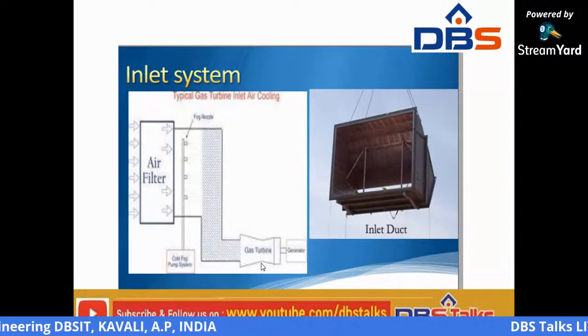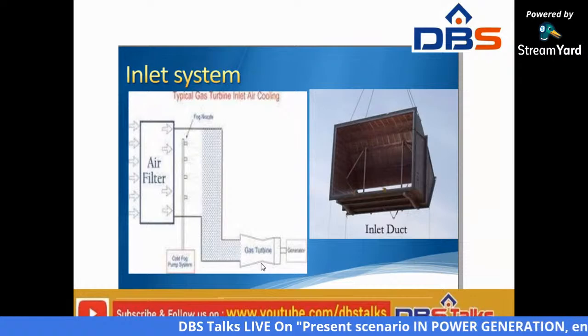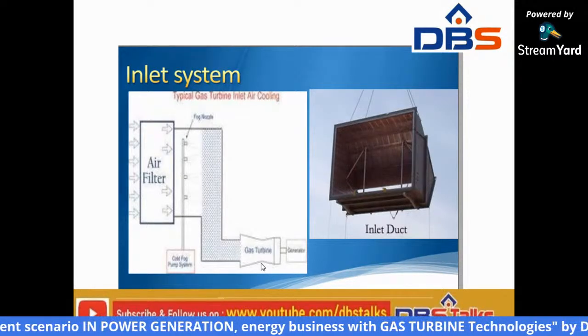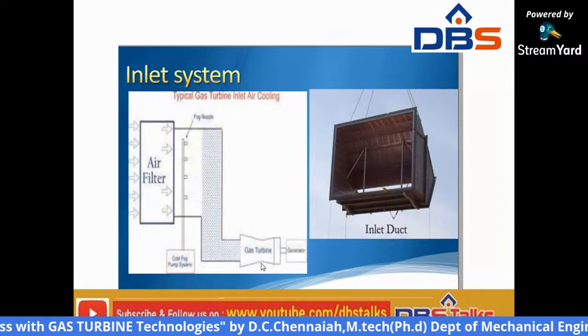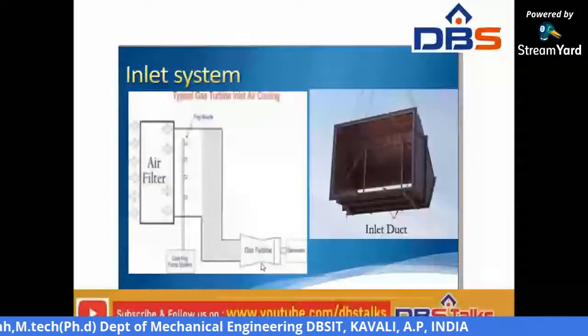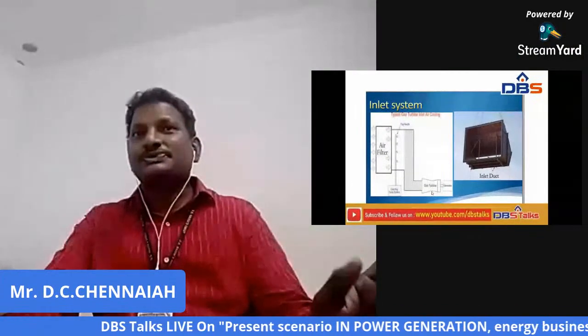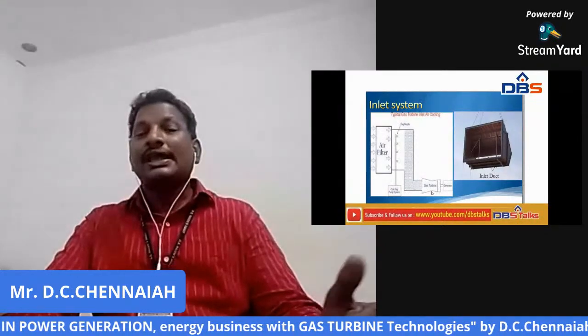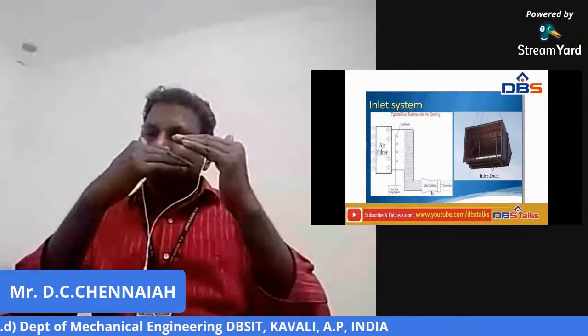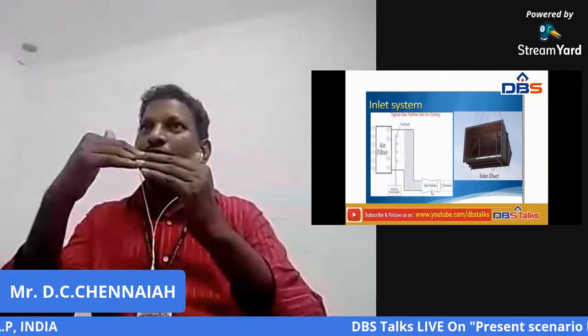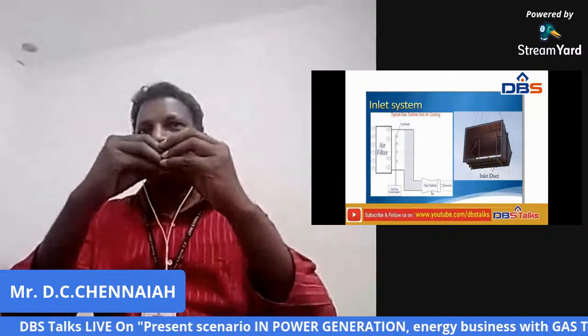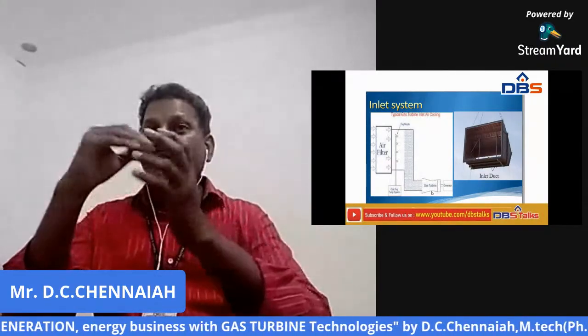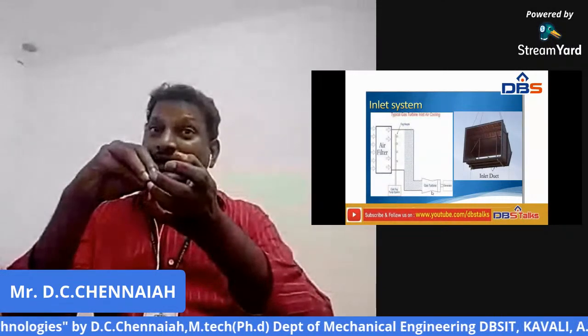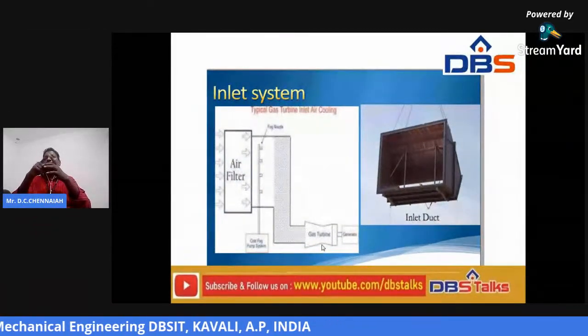Understand it this way: if 100% of the air is supplied, only 25% of the air is used for combustion of the fuel. The remaining 75% of the air forms a closed blanket over the turbine blades, because the produced higher temperature would otherwise cause damage to the turbine tips, the blade tips. If the turbine blade tip is damaged, its tip angle changes, and if the tip angle changes, the direction of gas entry row by row will change. So this tip clearance is very important, and by keeping safe working conditions for the turbine blade tips and maintaining certain mechanical properties, we use turbine inlet air cooling.